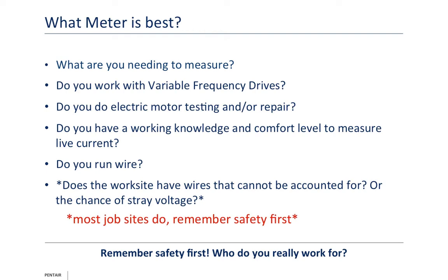Turn off the power to the device, your motor, your pump control, whatever. Have the power off. Connect the alligator clips to read the voltage. Set your meter to the highest reading, 600 volts, and set it down. So now you're not touching anything. Then turn on your power and look at your meter. Reason I mentioned that is if for some reason the power is not properly regulated and it goes over 600 volts, that meter might not be able to hold the insulation properly, and you could get shocked. So don't be holding it, okay?